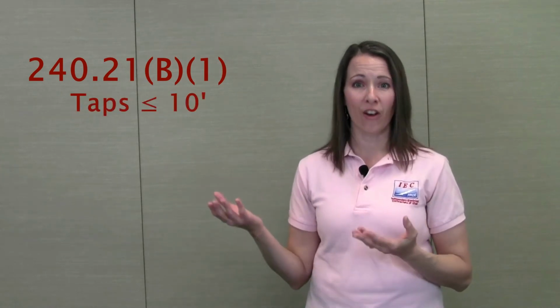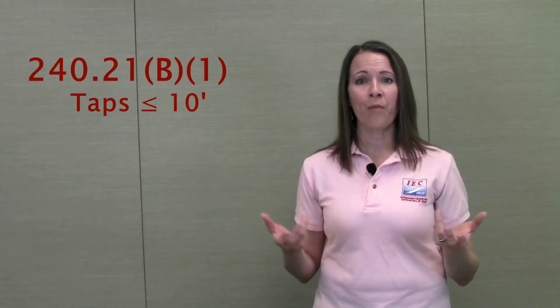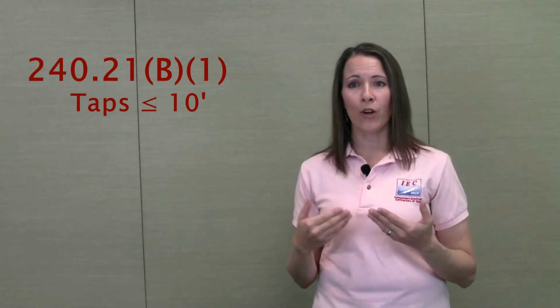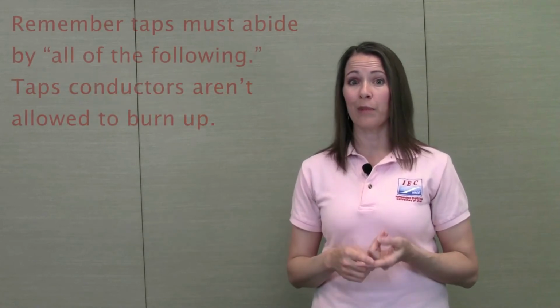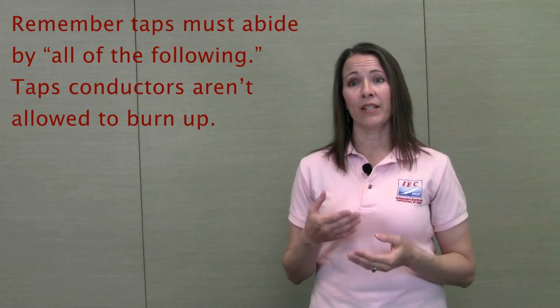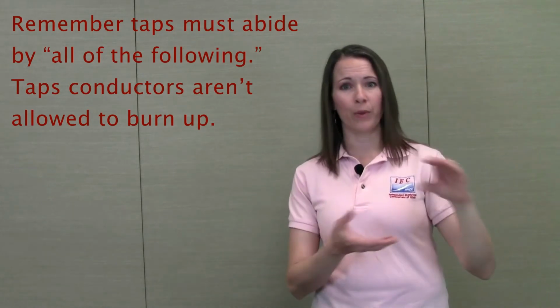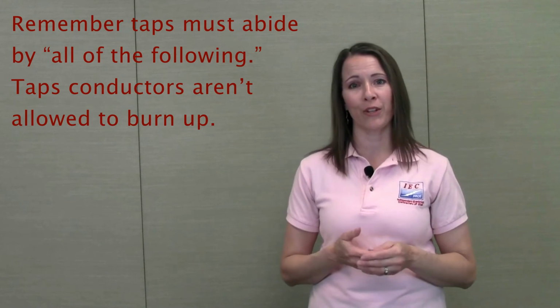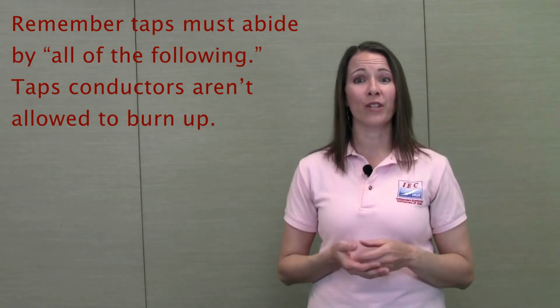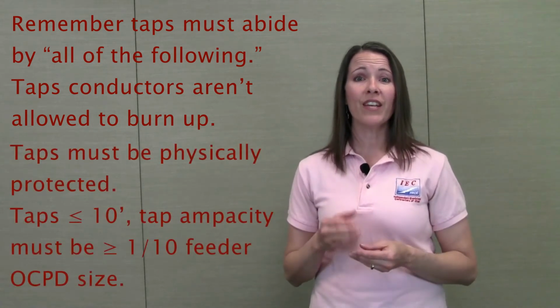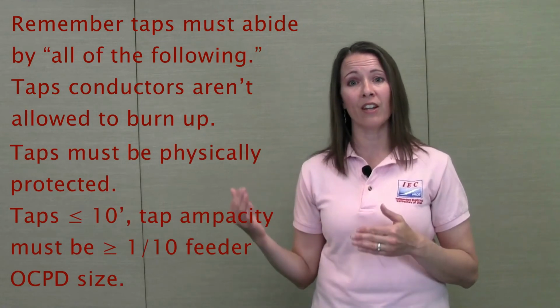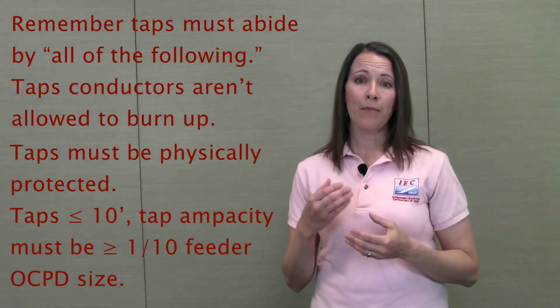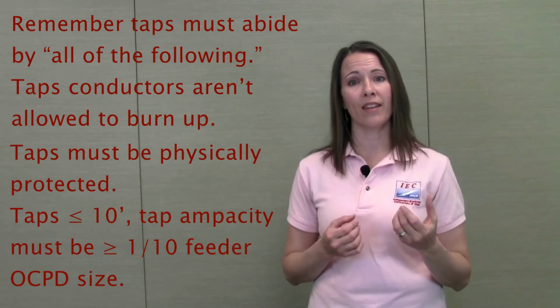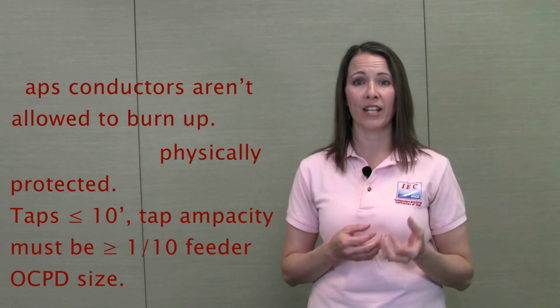240.21(B)(1) is for taps that are not longer than 10 feet long. Sometimes this is called the 10-foot tap rule. Just to make sense of some of these codes, remember that taps have to abide by all of the following. Tap conductors aren't allowed to burn up. That's what one of the subsections says. You can't put more load on this conductor than it's going to be protected from. Taps have to be physically protected. And for this rule, for taps that are 10 feet long and less, the tap ampacity has to be at least 1/10 of the size of the feeder overcurrent protection device.